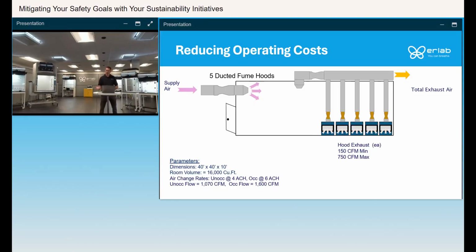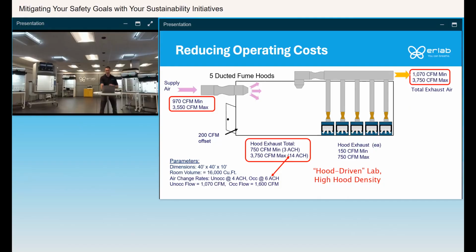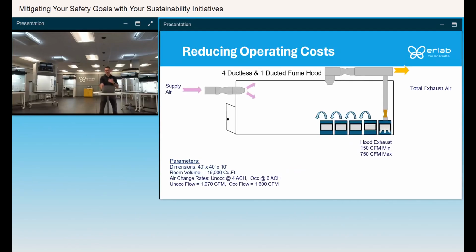So 6-foot hoods would be about 750 CFM. With each of them being on and operating, you need about 3,700 CFM to run that lab, which is going to equate to about 14 air changes per hour, which is 8 air changes per hour more than is needed. So that means in the summer, you're blowing out all that cool conditioned air. In the winter, that warm conditioned air will be blown out as well. You have to have more makeup air, so that gets very expensive.